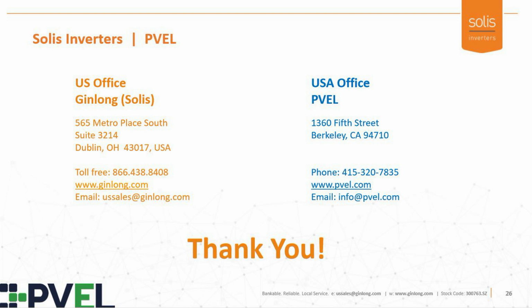That's a great question. As we mentioned with the downstream partner steering committee, we continue to update parts of our testing strategy to keep them relevant with new functions and features of inverter products, or as hybrid products that combine storage and PV together. In addition, there are many working groups around power electronics reliability, and we stay close to those in terms of concept and what wear-out mechanisms we're testing for. That results in a yearly or every-18-month update to our product qualification program. Most of the time those changes are minor, they could be duration changes based on test data we've seen over the last 18 months, but sometimes they include more major revisions to make sure we're capturing that functionality. An example would be California Rule 21 and low voltage ride-through, to make sure we're addressing how these products respond under those scenarios.